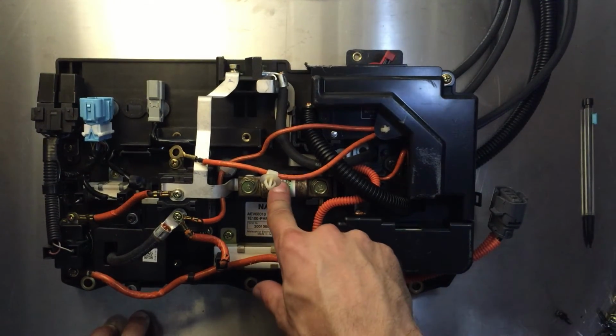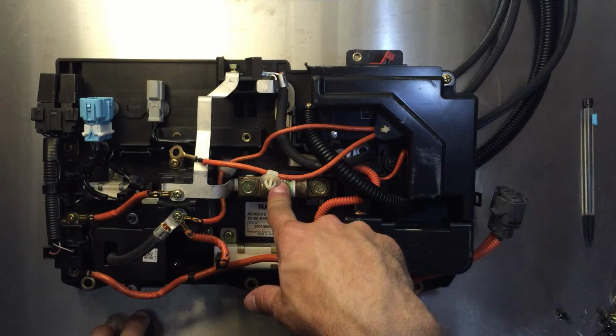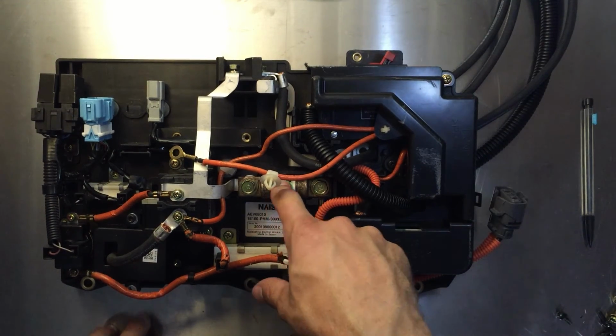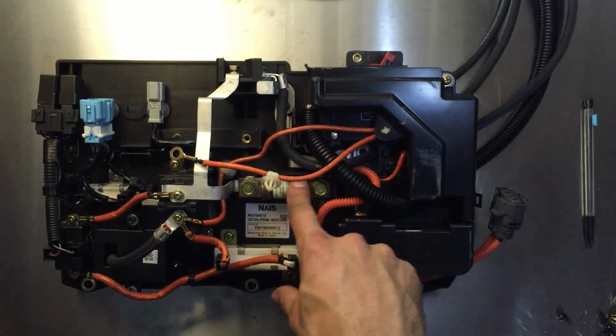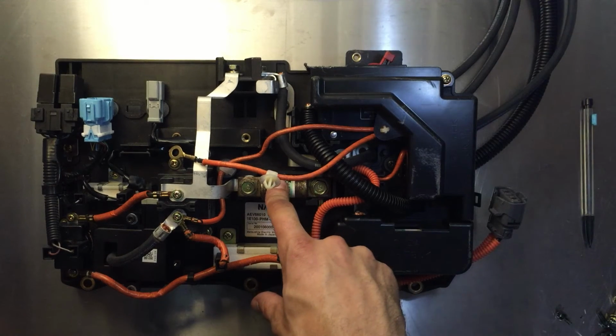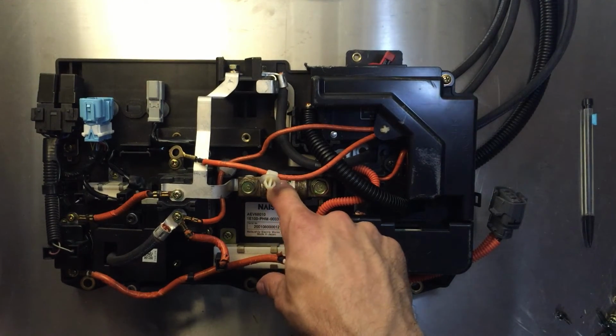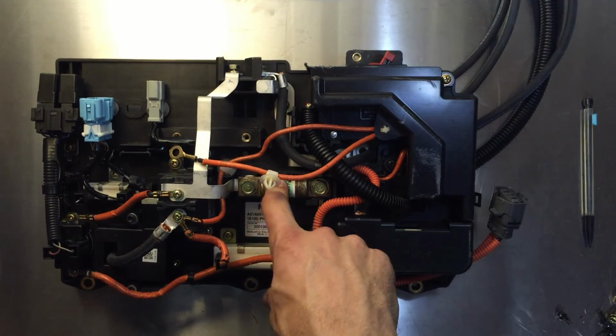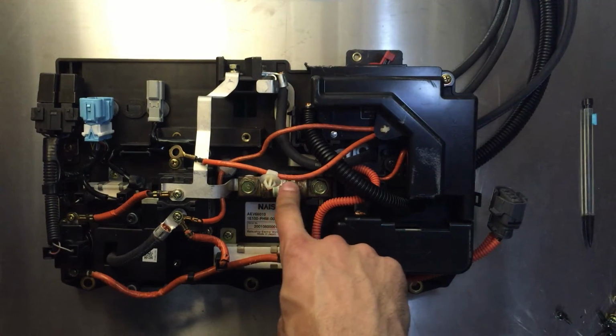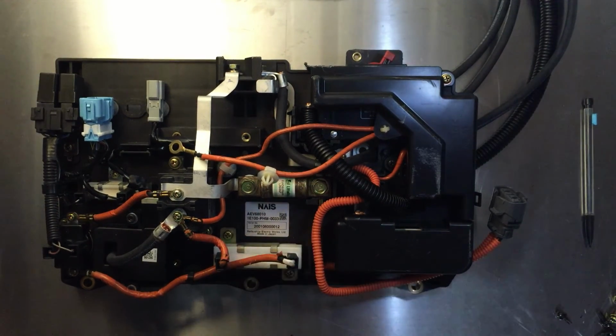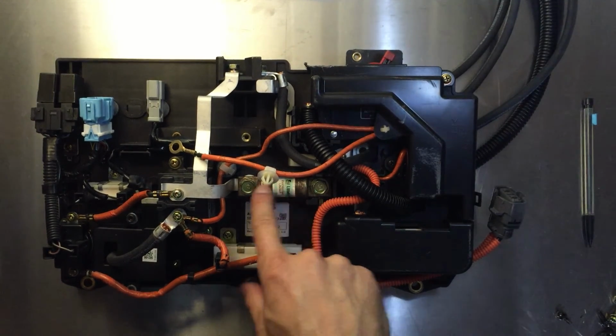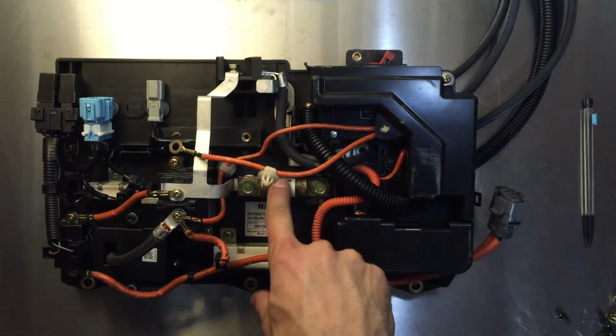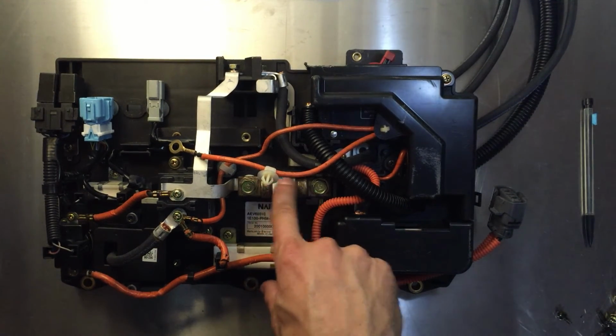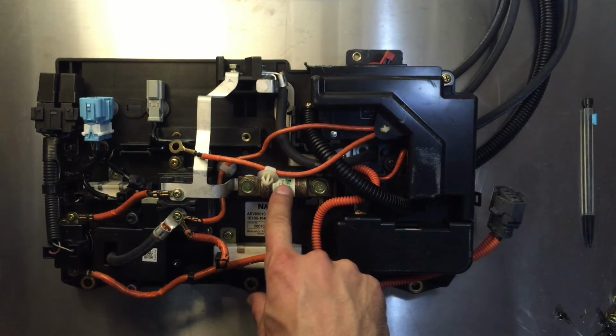The voltage rating on a fuse is very important. A lot of people say a 30 amp fuse just means current breaks it, but the problem is what happens when you blow that fuse. If you use a 12 volt SAE blade fuse, blowing it out can sustain an arc and keep burning because the parts are too close together, giving you a high voltage spark. These are ceramic, sandglass bead fuses, which suppress that spark long before anything catches fire.